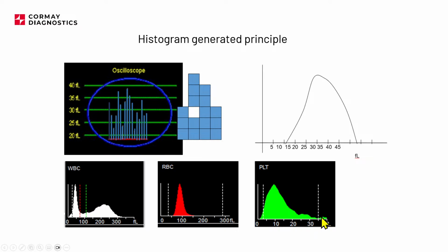For the PLT channel, we also count the total number of PLTs. The device can also calculate the MPV, which is the mean platelet volume. So it's a parameter similar to this one, but it's about the PLTs. The device can also report parameters like PLCR, and PLCR is the percentage of platelets bigger than 12 femtoliters. So everything on this side, from roughly somewhere here, will be the PLCR percentage. And there is also the PDW. So this is also the width of this histogram. And other parameters are basically calculated according to the data which was recorded by the device.